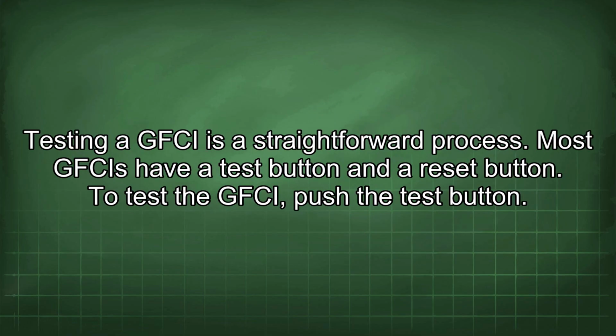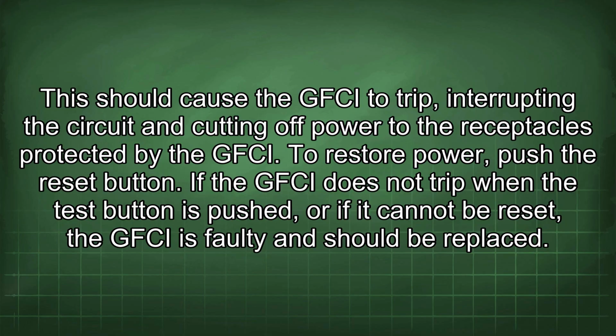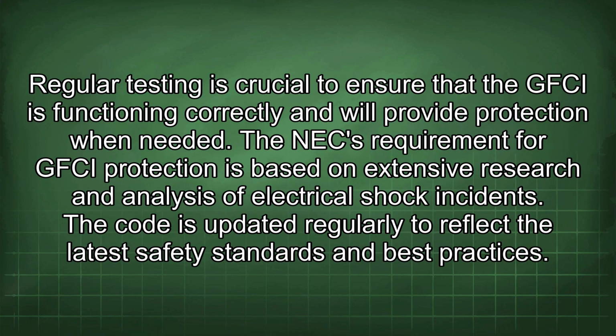Testing a GFCI is a straightforward process. Most GFCIs have a test button and a reset button. To test the GFCI, push the test button. This should cause the GFCI to trip, interrupting the circuit and cutting off power to the receptacles protected by the GFCI. To restore power, push the reset button. If the GFCI does not trip when the test button is pushed, or if it cannot be reset, the GFCI is faulty and should be replaced. Regular testing is crucial to ensure that the GFCI is functioning correctly and will provide protection when needed.